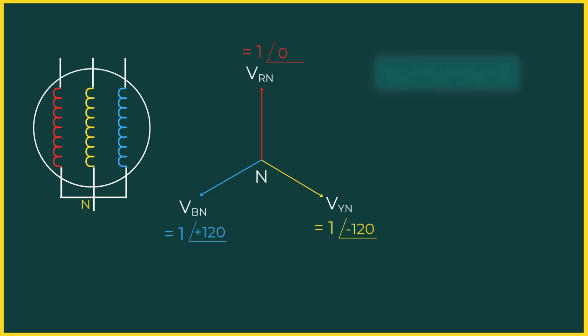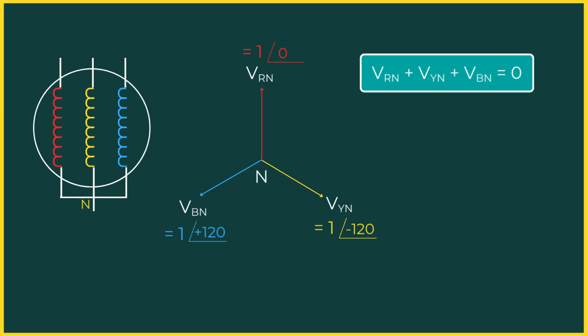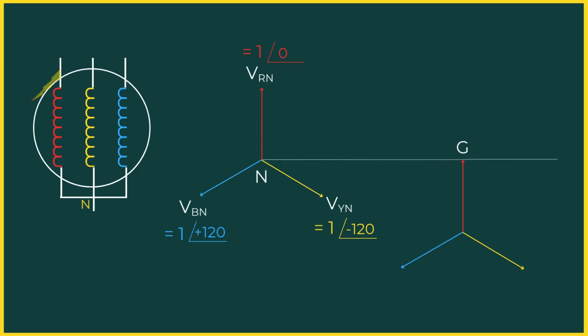Under normal conditions, the three-phase voltages VRN, VYN, and VBN are perfectly balanced and spaced 120 degrees apart. Considering each phase with a magnitude of 1 per unit, the vector sum of these phasors is 0, which keeps the neutral point at ground potential. Now, imagine a terminal fault occurs on the R phase of the stator winding. The voltage of the faulted R phase drops to 0, while the healthy Y and B phases rise to line voltage. As a result, the neutral point shifts away from ground potential, producing a neutral voltage displacement.